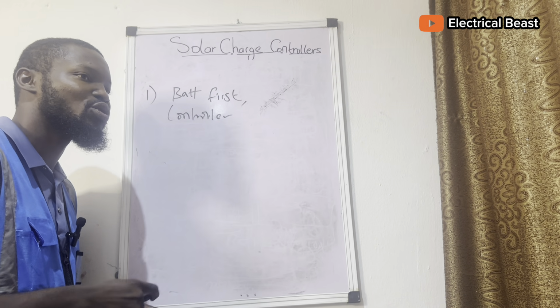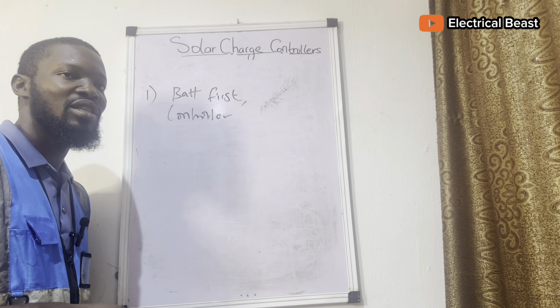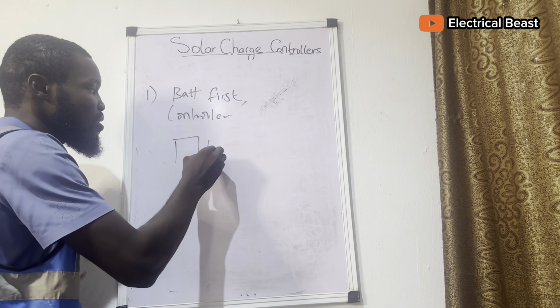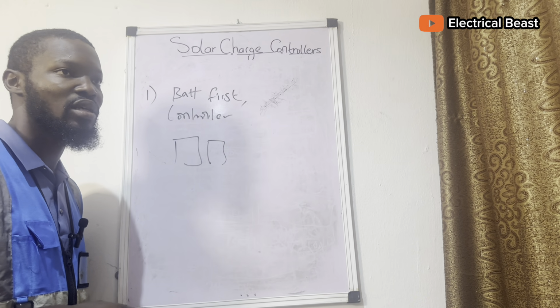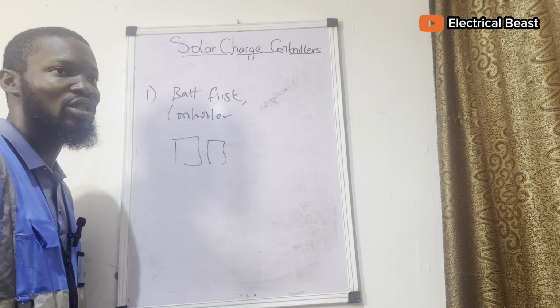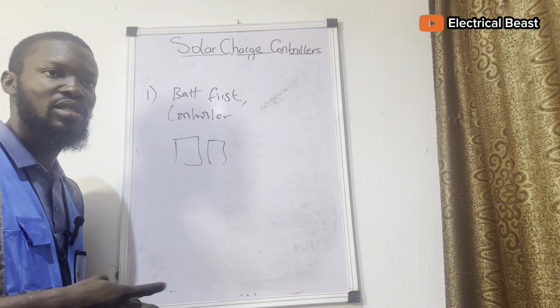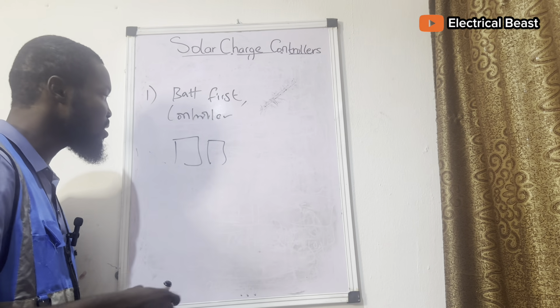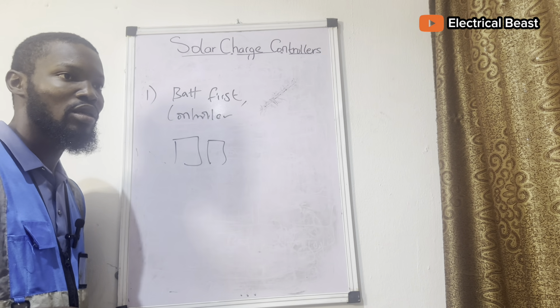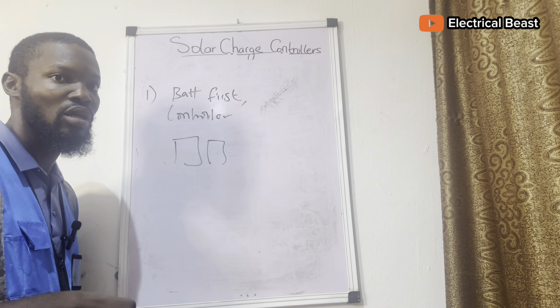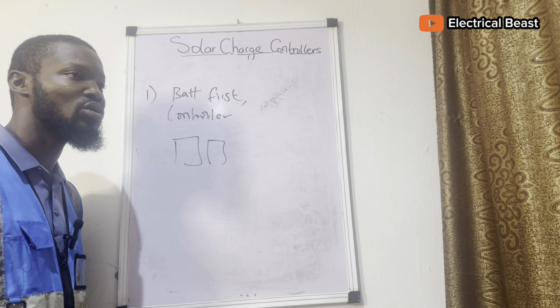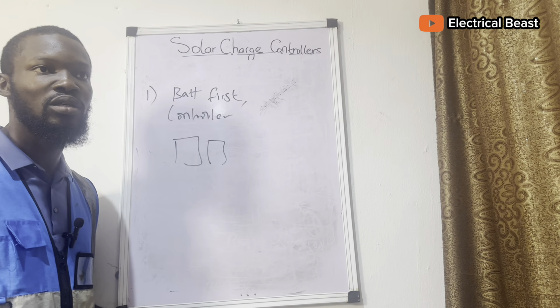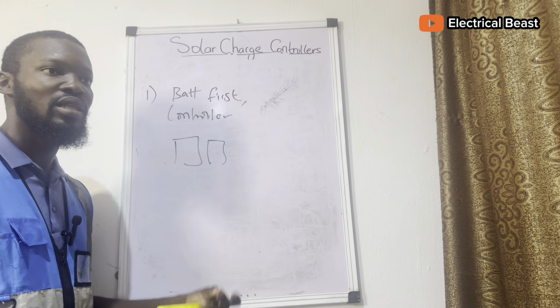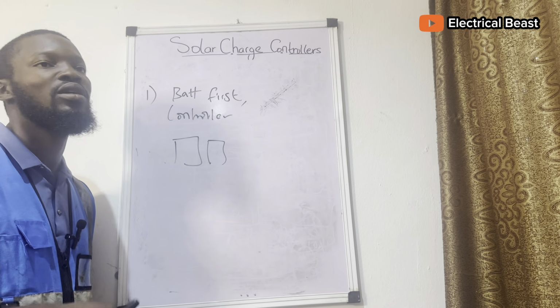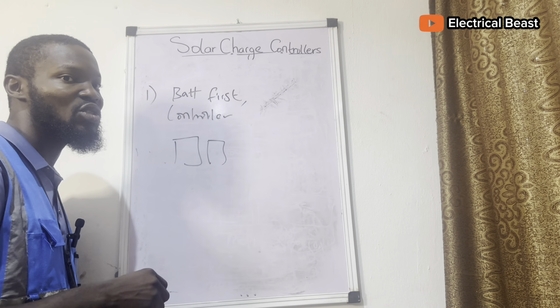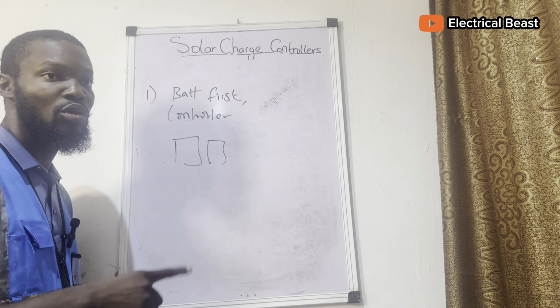If you connect the panels to the controller without connecting the battery, especially for a high voltage system like a high voltage inverter, there's no problem. You can connect the panels to the controller side, and those kinds of systems work without a battery. But for systems that use an external charge controller, before you connect your panels to your charge controller, you ensure that the battery connection has already been done, so that when you connect, the controller reads the voltage of the battery, and then there's a communication between the panels, the controller and the battery for everything to charge properly. If you miss that step, you're going to destroy the controller.